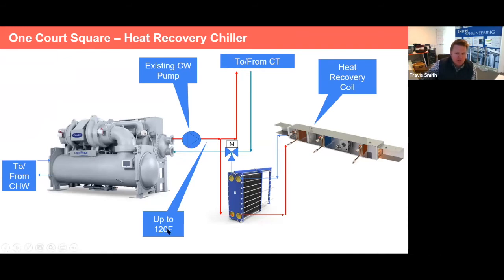degrees Fahrenheit. So we have a lot of experience with heat pump chillers, involved in Stanford's project, and we're involved in the Princeton Tiger project, which is electrification of Princeton University. So we have a lot of experience with this industrial level heat pump. So what we would do is stop utilizing free cooling, run this heat pump chiller, heat recovery chiller technically in this situation, and take the heat off of that 120 degrees and put it into the existing energy recovery coil on the DOAS air handling units.